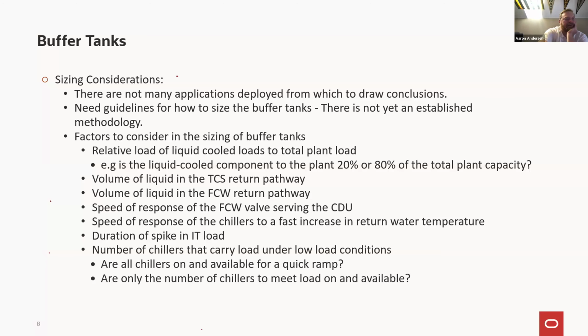Just a commentary. Huge fan of buffer tanks, or at least thermal storage, for a number of reasons. I've led two major data center efforts where we were heavily liquid cooled. We built thermal capacity in intentionally for slightly different reasons. Both facilities don't have chiller plants, right, and size things based on ride through of bad wet bulb days.